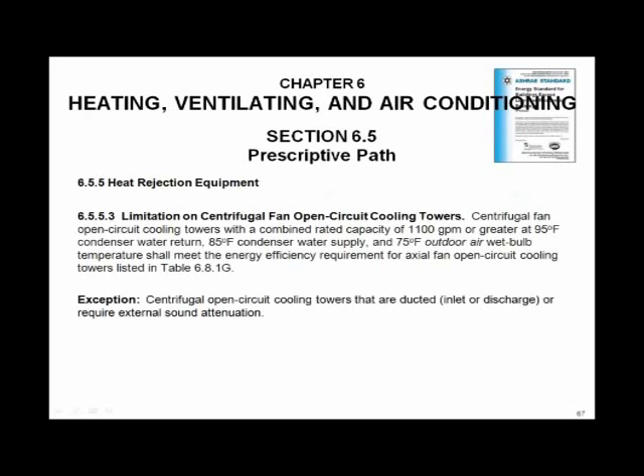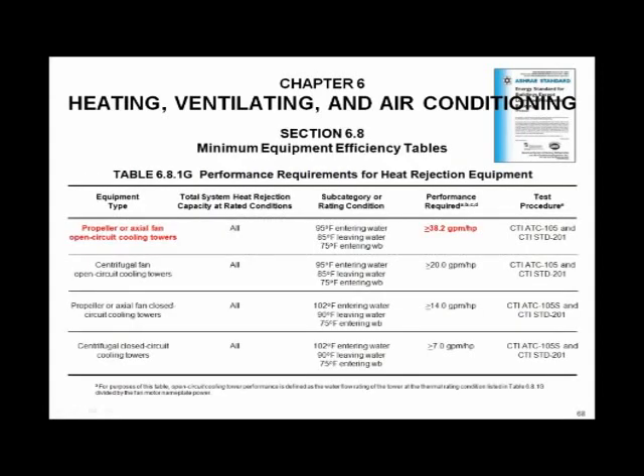A couple other rejections of BTUs for towers. We won't worry about too much, but there's some numbers in here based on the minimum GPM to a cooling tower per fan horsepower of the tower. And here's an example for you in red. 90.1 2010 was 38.2 minimum GPM per fan horsepower through a cooling tower. Now, 90.1 2013, that number went up to 40.2 GPM. Now, I've seen specifications on the West Coast that number might be as high as 80 or 90 GPM per fan horsepower. So what they're going to do is they're going to make you have bigger boxes in your cooling towers, less horsepower per flow, and this is going to be the efficiency of the tower.